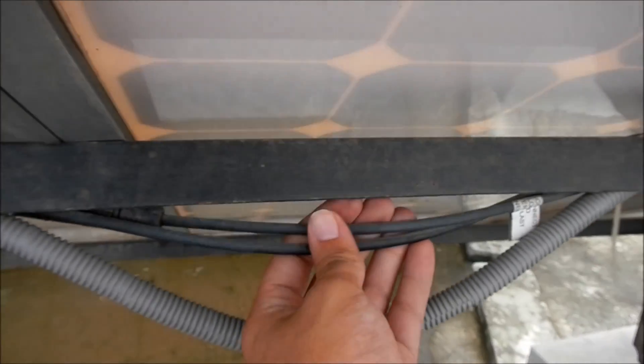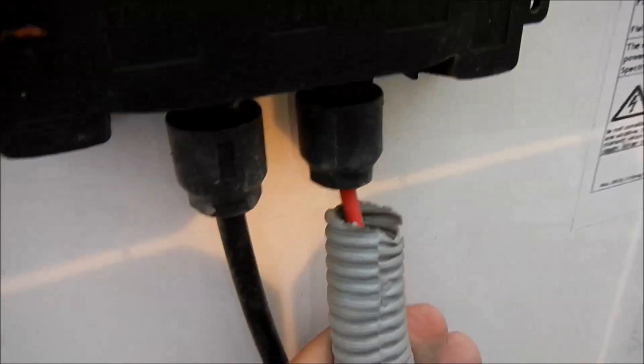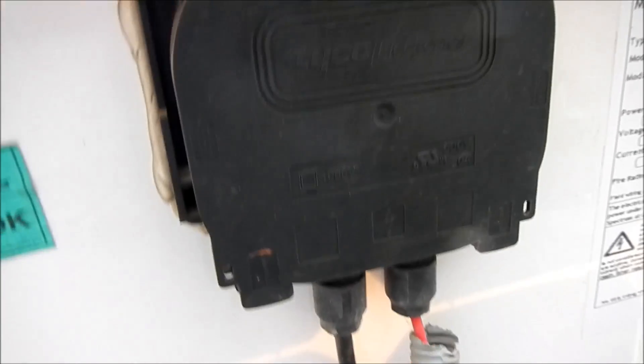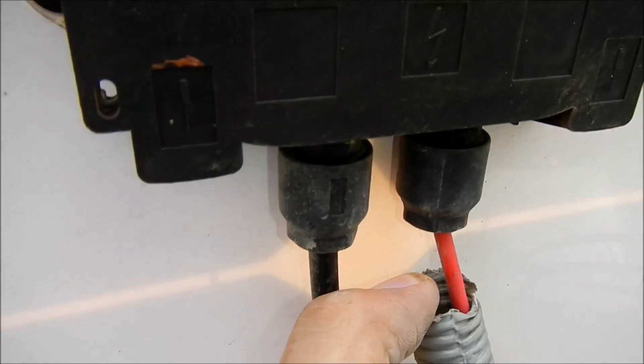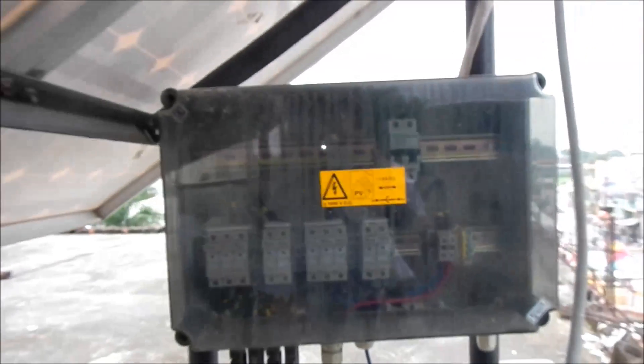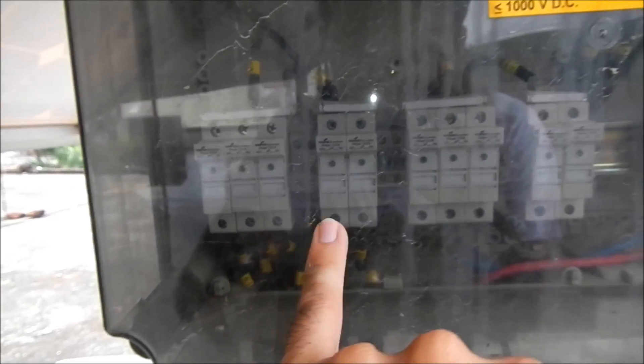That's the back of the solar array. There's solar wire here, but some of the other wires are just protected in what appears to be a loom. Again, this is a wire that's been spliced into the solar junction box. It doesn't appear to be USE-2 solar wire, but it's protected only by this loom.